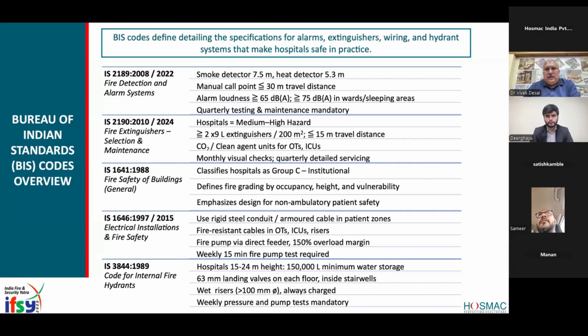Understood. Then, there are certain norms about the internal fire hydrants and water storage. So hospitals which are less than 24-meter height need minimum 150,000 liters of water. And then there are other norms which go beyond. Landing valves, wet risers, they should always be charged. So how do we keep that always charged, Satish? Yeah, so first thing regarding the water tanks, whenever there is a larger spread hospital, the fire NBC has a norm that if the fire hydrants quantity is more than 100 numbers, one has to double the capacity of the fire tank.